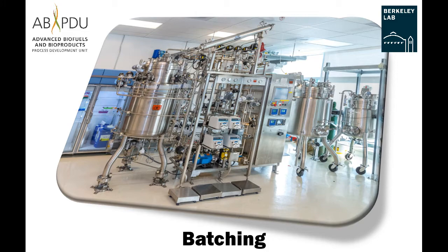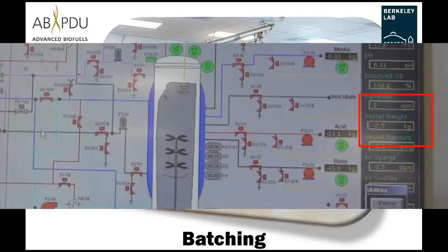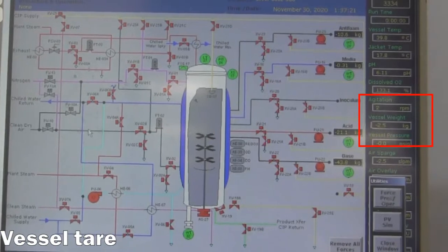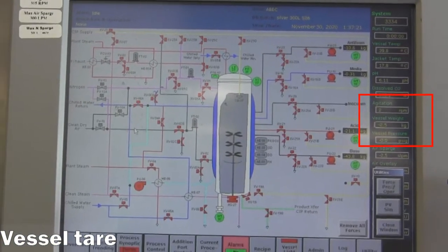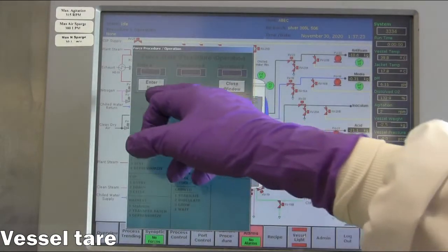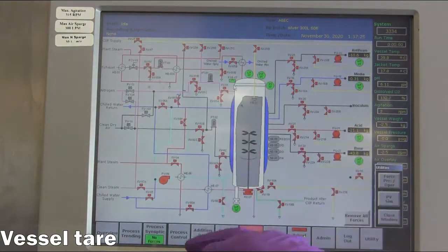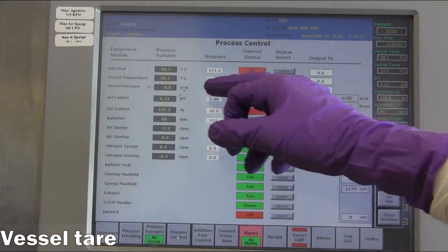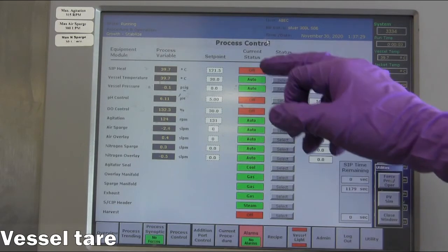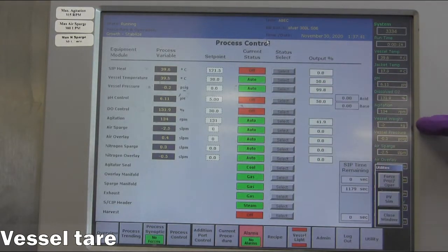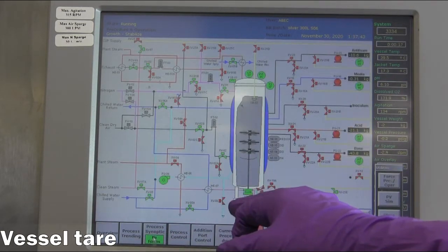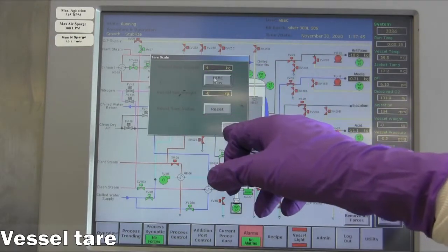Batching. Before media components can be added to the reactor, the load cell that is used to track the vessel weight needs to be tared. Enter the growth mode and prime the jacket to get the correct tare weight. Tare the load cell and return the reactor to idle mode.